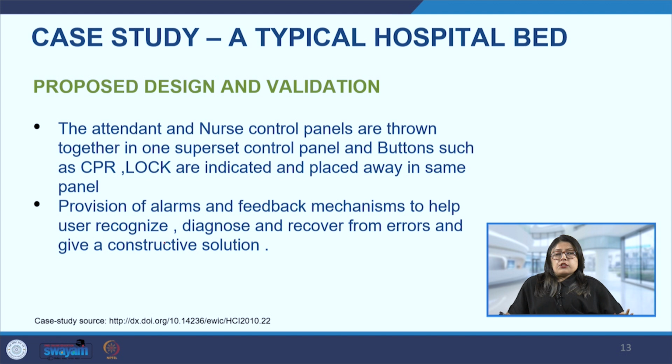Now, the next intervention that was undertaken was that the attendant and the nurses control panels were combined together into one superset control panel, and buttons that were very crucial like CPR and lock are indicated and placed away in the same panel, because these are the critical ones that will be used by the attendant and the nurse, and both of them are trained personnel. So of course the nurse conducts all of these life saving actions, but the attendant can also equally participate.